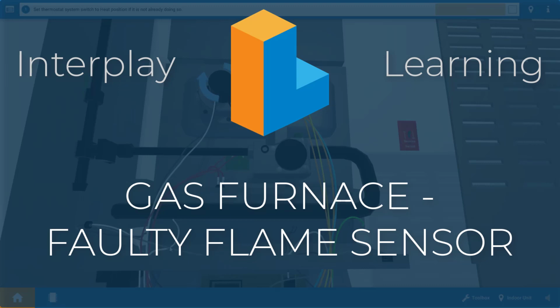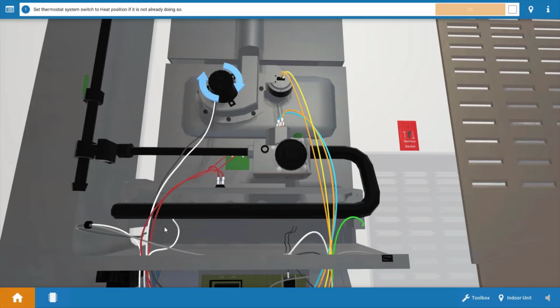Now, the flame sensor shown here over on the left, this white wire, is part of the flame rectification process, meaning that a small alternating current signal is sent through this white wire to the flame sensor from the integrated furnace controller, IFC. When the flame envelopes the sensor, this signal passes through the flame and rectifies, or changes, to DC, hence the term flame rectification. That signal then picks up this green ground wire over here that's bonded to the burners and carries that signal back to the IFC, proving that there's a flame present.